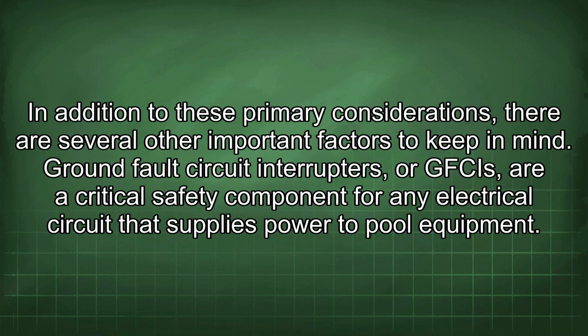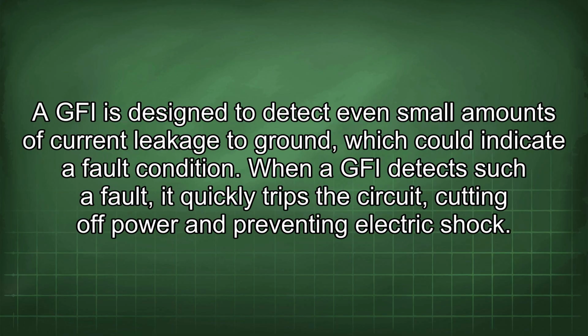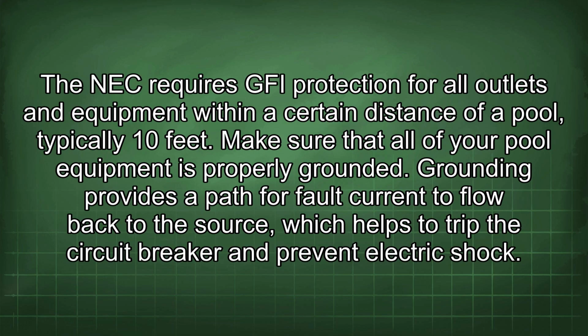In addition to these primary considerations, there are several other important factors to keep in mind. Ground fault circuit interrupters, or GFCIs, are a critical safety component for any electrical circuit that supplies power to pool equipment. A GFI is designed to detect even small amounts of current leakage to ground, which could indicate a fault condition. When a GFI detects such a fault, it quickly trips the circuit, cutting off power and preventing electric shock. The NEC requires GFI protection for all outlets and equipment within a certain distance of a pool, typically 10 feet.